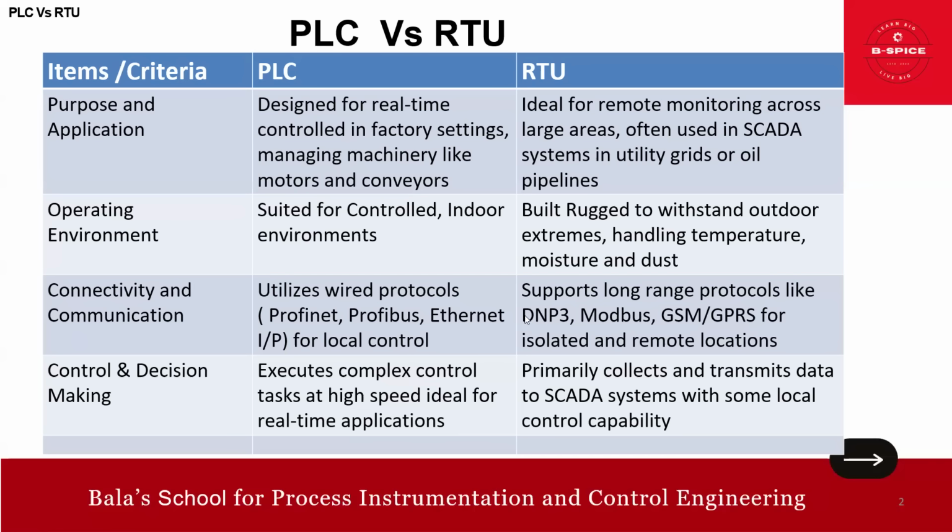Coming back to the RTU, it supports long-range protocols like DNP3, Modbus, GSM, GPRS, for isolated and remote locations. In one of our videos we also highlighted DNP3. You can watch and benefit. So on connectivity and communication, PLC focus is more on Profinet, Profibus, whereas the RTU supports long-range protocols like DNP3 and Modbus.